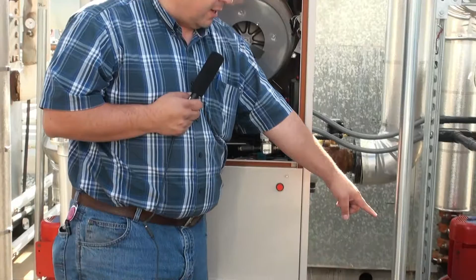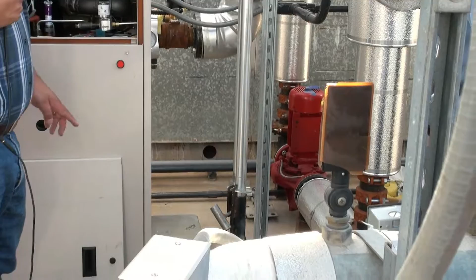Since it doesn't matter which boiler, they're all the same. If you look at that, there's the screen that goes into the pump to protect the pump. If you pop it to clean that screen and the water loses flow, the boiler's going to trip out on the flow. So I would prefer that if you're going to do any cleaning or draining, you turn the boiler off, and I'll show you how. That way, if you turn the boiler off and do the work, it never picks up a fault. Okay, so there's an on-off switch.